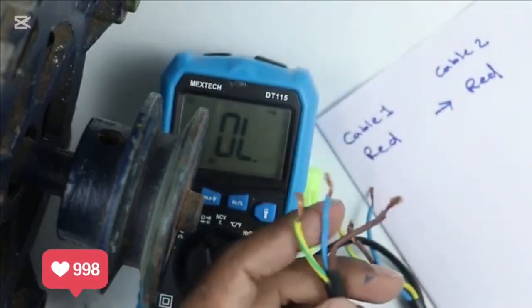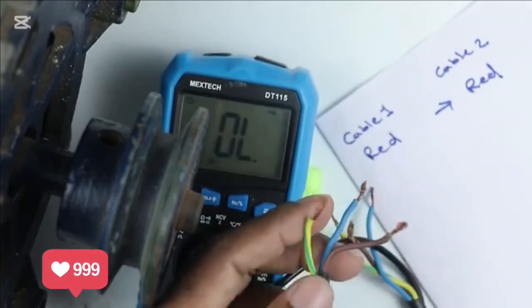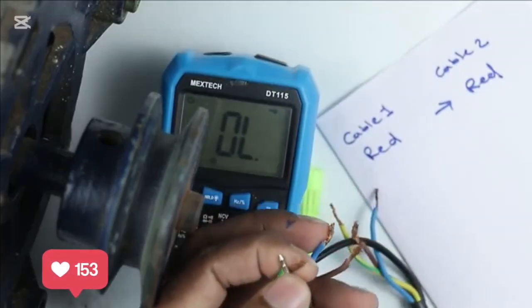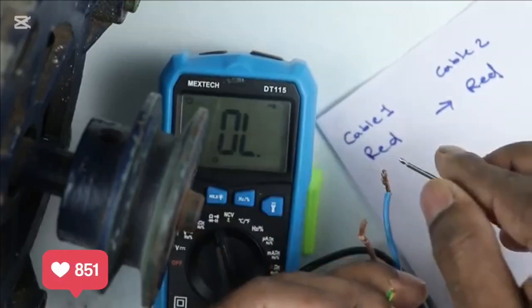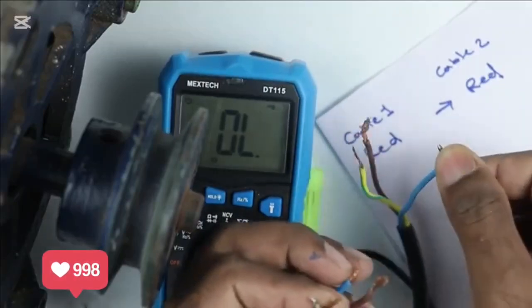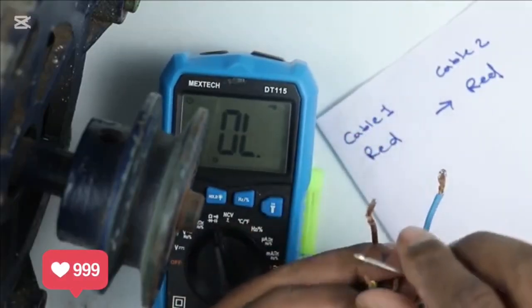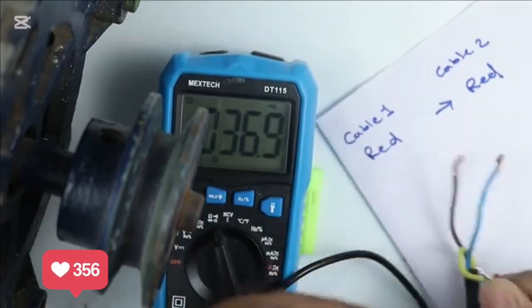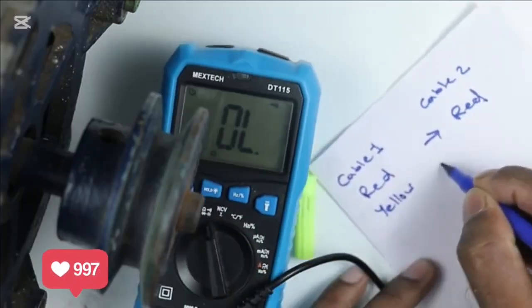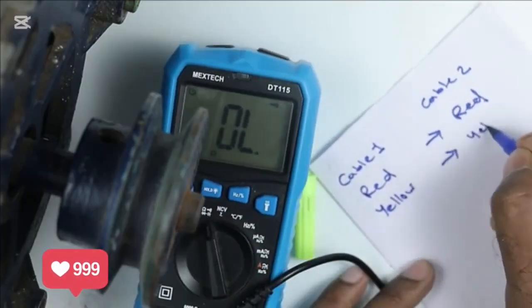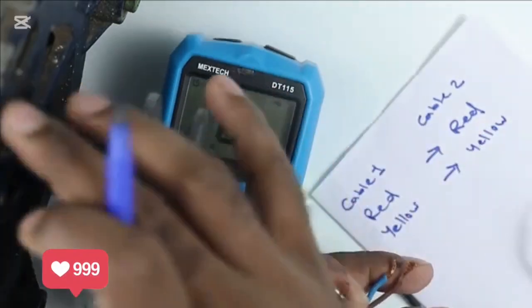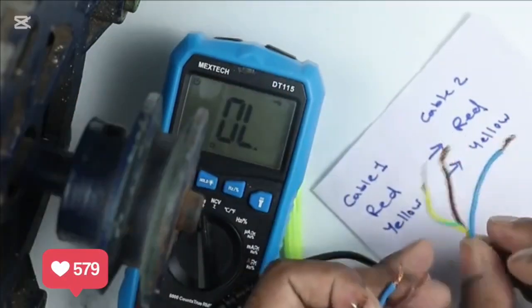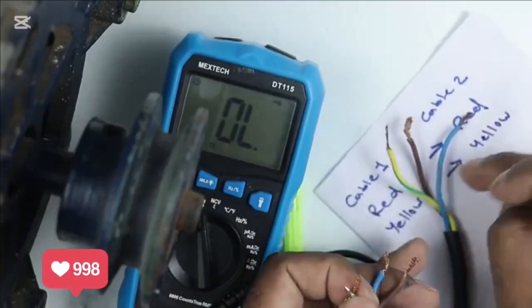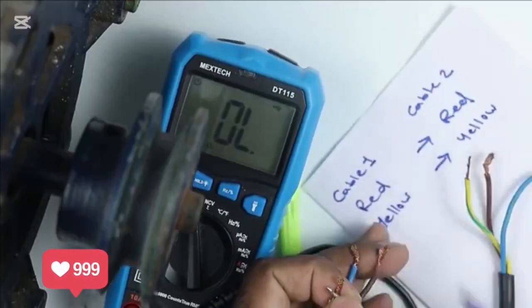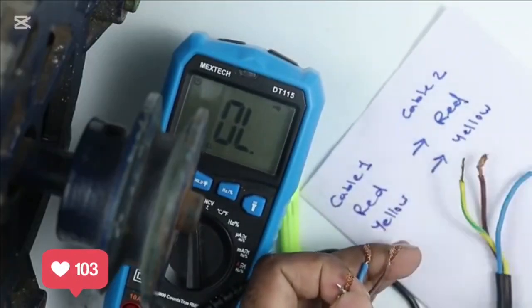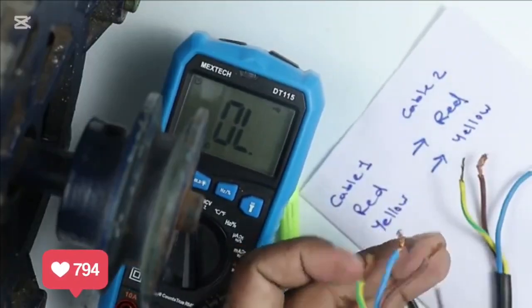In the second wire also we will check the continuity. Connect one probe to the yellow wire and the other probe to a wire in the other cable. I am connecting with the blue wire here. You can see I am not getting any continuity. Let's check with yellow. Here I am getting continuity. This means the yellow wire has continuity with the yellow wire of cable number 2. It may be possible that the wires of the cables coming from the motor give continuity randomly with any wire. Here we are getting continuity with the same color wire, but it may be different in your case. So it is important to check this.